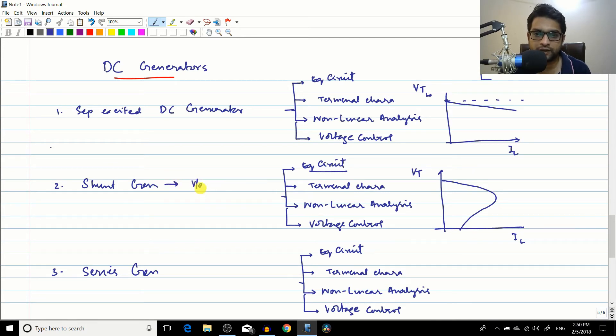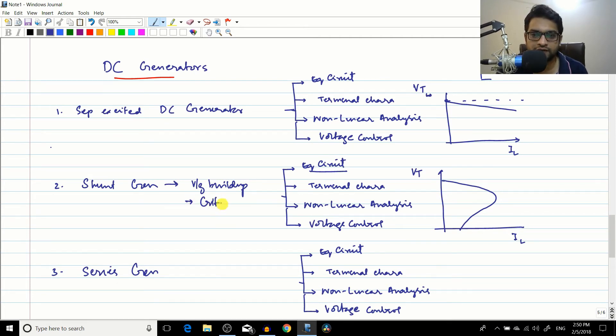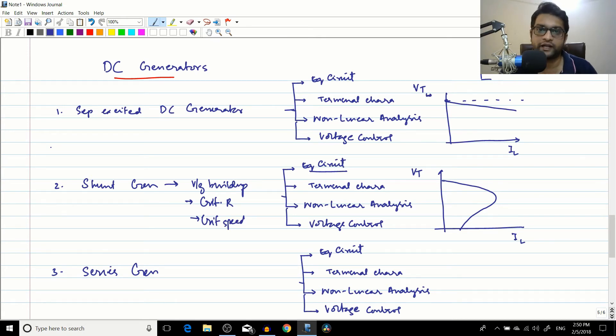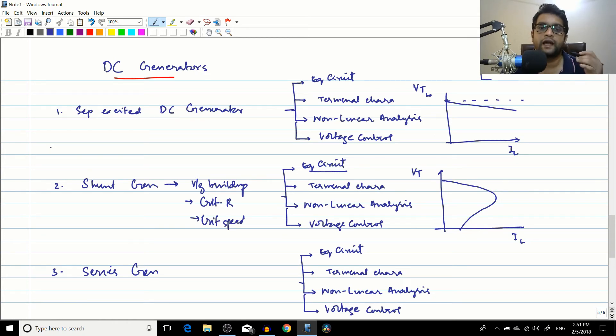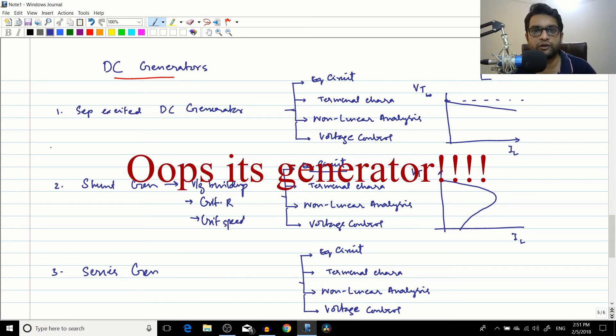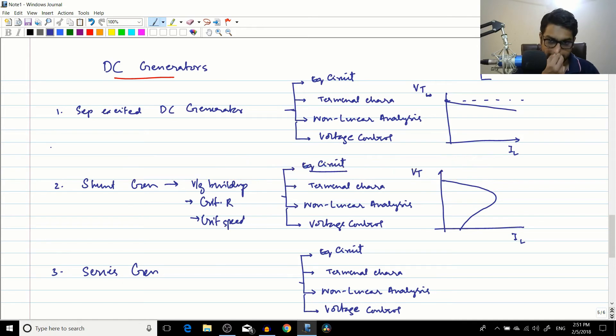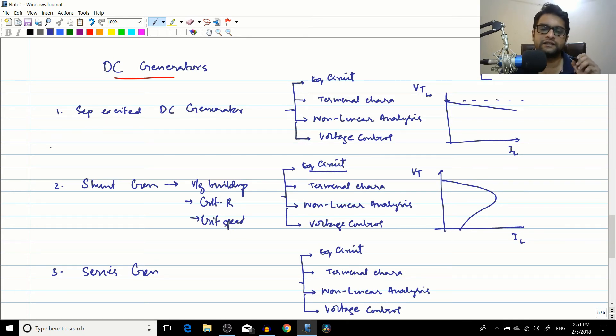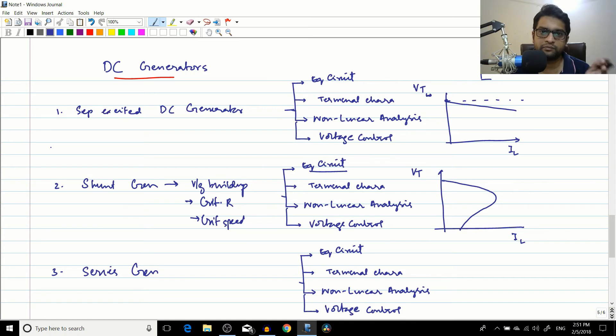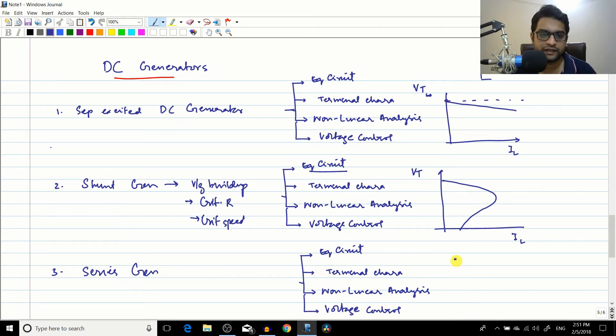For the shunt generator, we studied voltage build-up and introduced the concepts of critical resistance and critical speed. The field winding resistance must always be less than the critical resistance, and the machine speed must be above the critical speed, for voltage build-up to occur. Critical resistance is the maximum resistance beyond which the generator will not self-excite; critical speed is the minimum speed below which the machine will not excite.